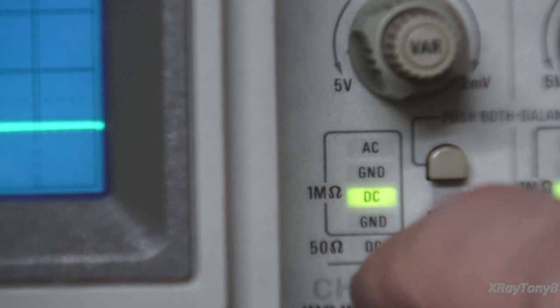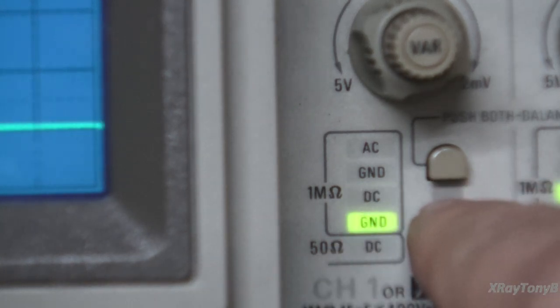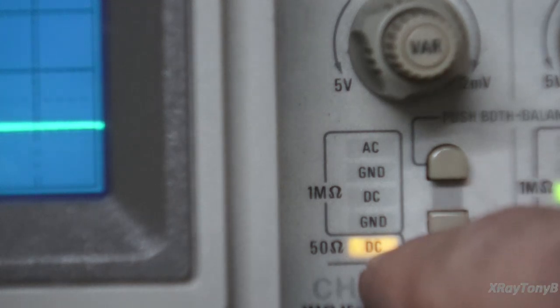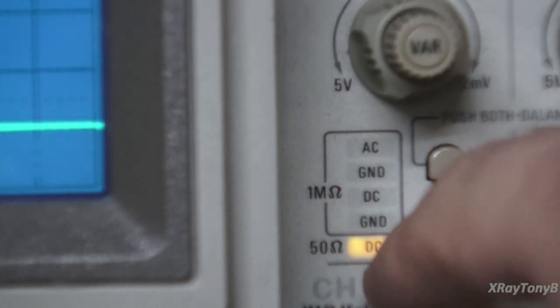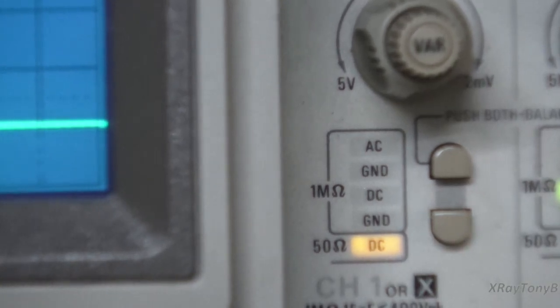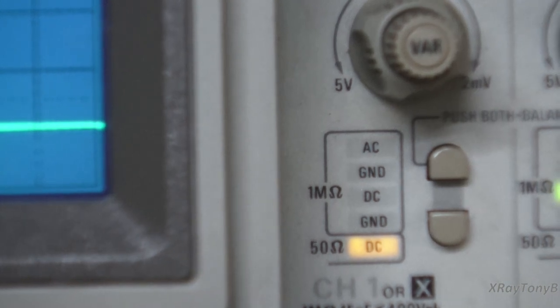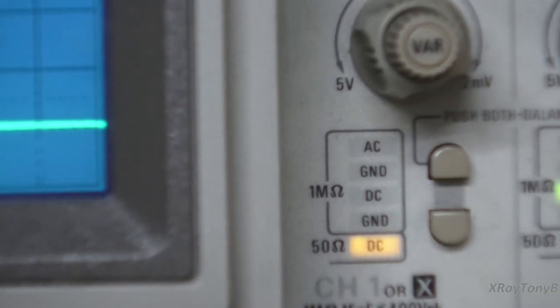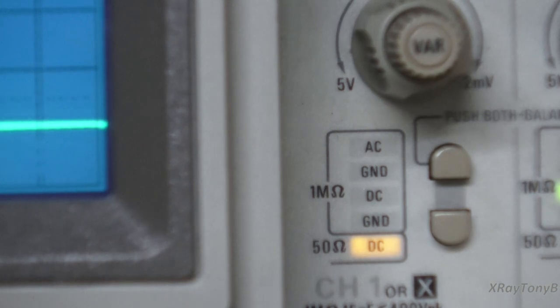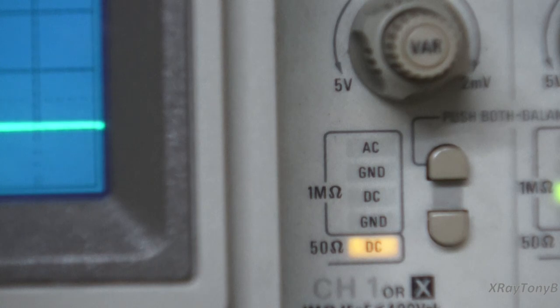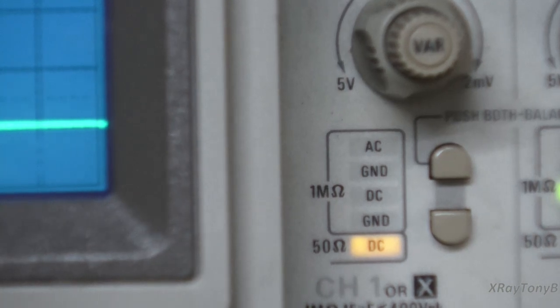But again, what this means is when I switch down to here, and you notice it turns a different color as well, it's not green, they really want you to know what you're doing. Use this with extreme caution. That's actually putting a 50 ohm termination. It's like putting a 50 ohm resistor across this probe. And why would you ever want to do that? Well, remember I told you this is a high impedance device. It's looking at, you know, mega ohms and mega ohms between the scope. You know, the scope doesn't really pose any load to anything. It's a very small load. But when we switch it to 50 ohms, all of a sudden it looks like a 50 ohm load.